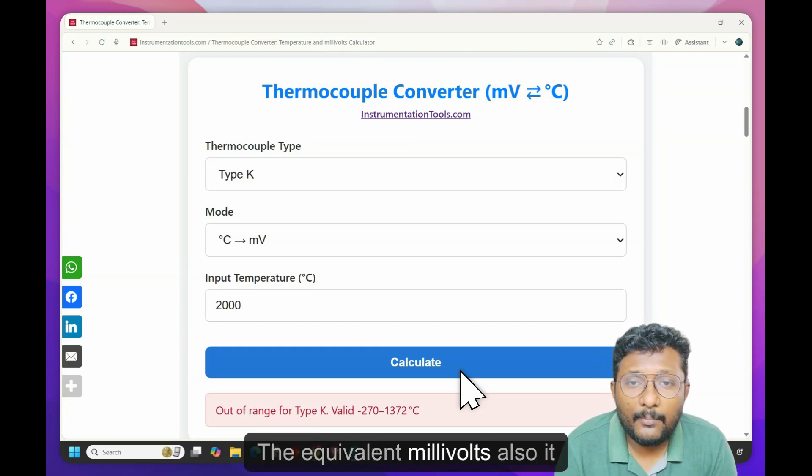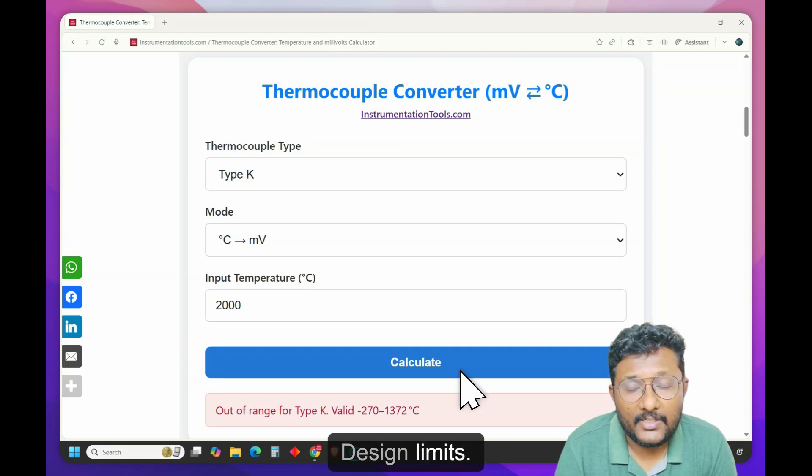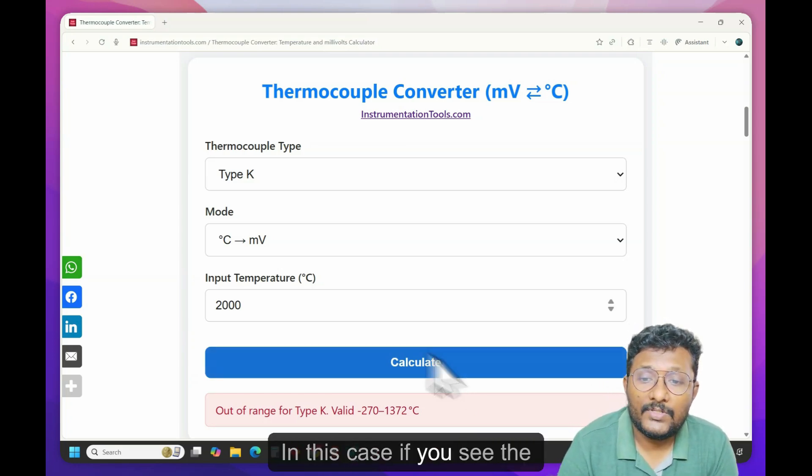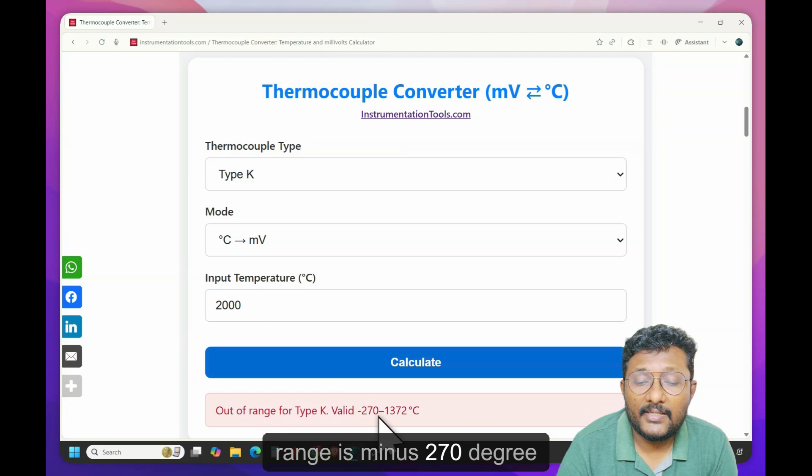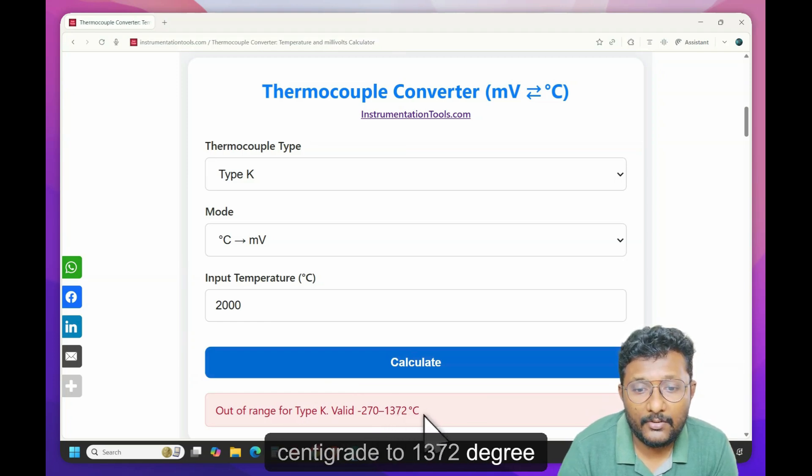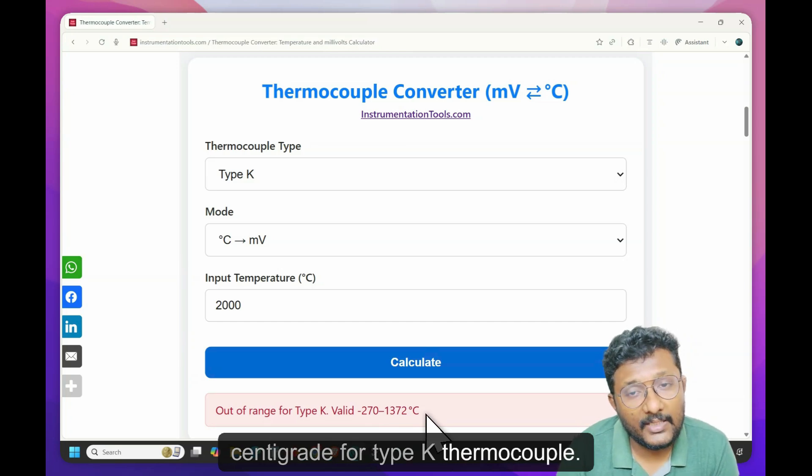So we have fixed temperature scale at the same time. The equivalent millivolts also, it is within the limits, design limits. In this case, if you see, the range is minus 270 degree centigrade to 1372 degree centigrade for type K thermocouple.